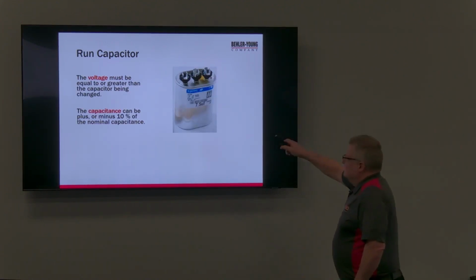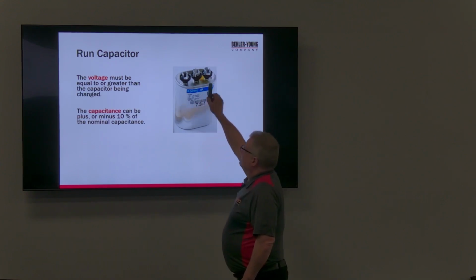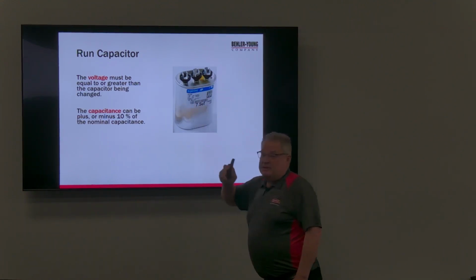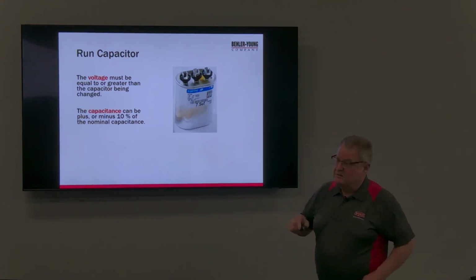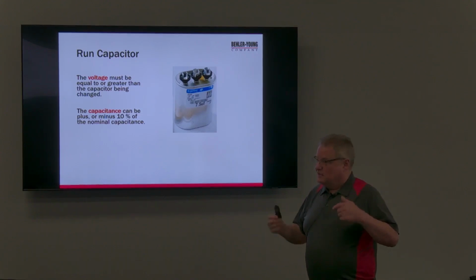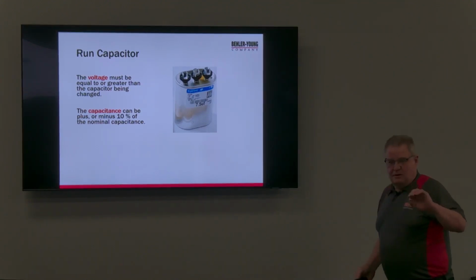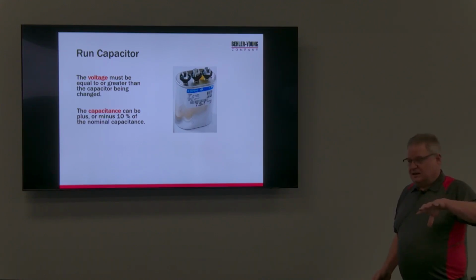This is a dual run, so this is actually two capacitors, one for the fan, one for the compressor. Now, be careful when you wire these in, because if you miswire these, you can actually make the motor run backwards. So if you get a fan motor running backwards, double check that capacitor wiring, because if you get it reversed, you can make them run backwards.